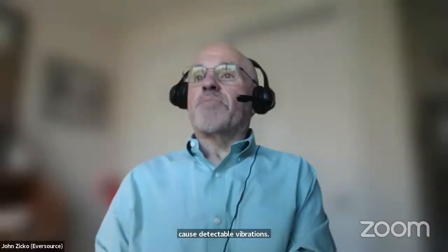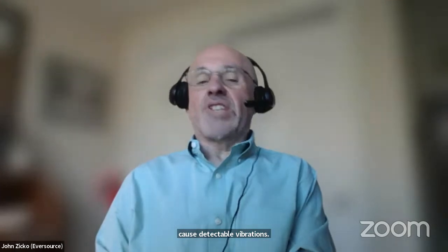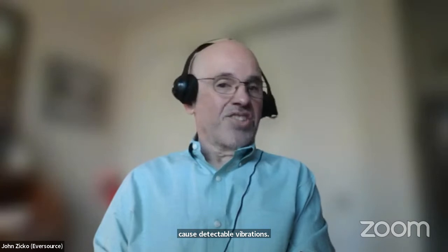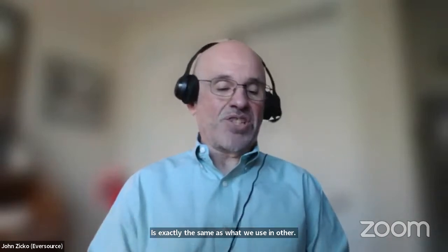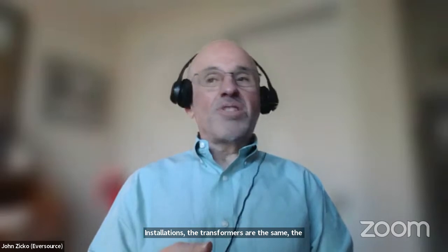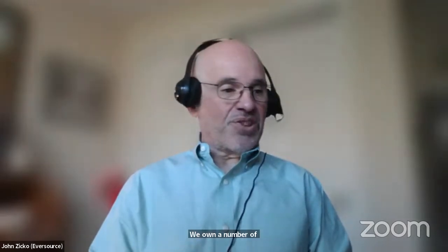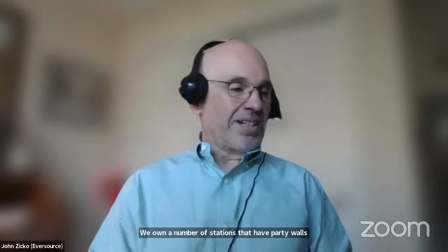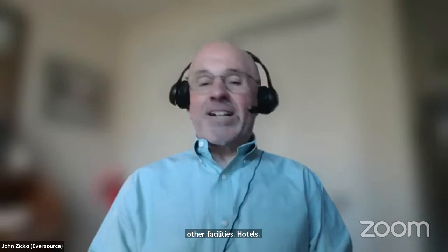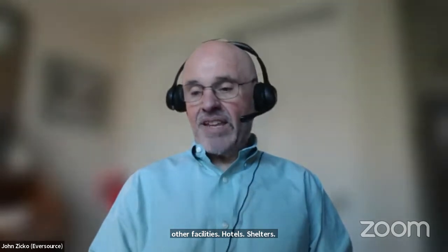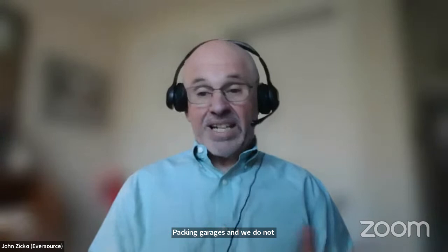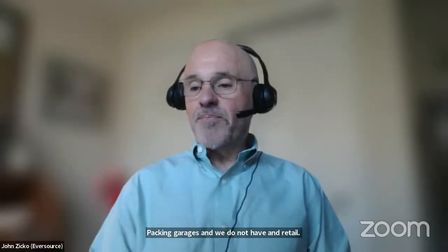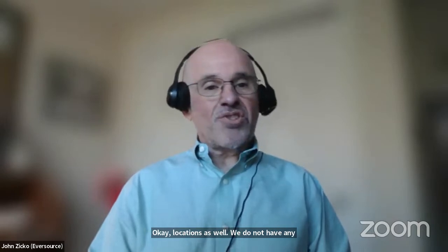No, I didn't intend to say that at all. The equipment that's going to be in the substation, segregating out the emergency generator for one moment, is exactly the same as what we use in other installations. The transformers are the same, the reactors are the same, the switchgear is the same. We own a number of stations that have party walls with other facilities, hotels, shelters, parking garages, and retail locations as well. We do not have any complaints of vibration from those, so we're basing it on that.